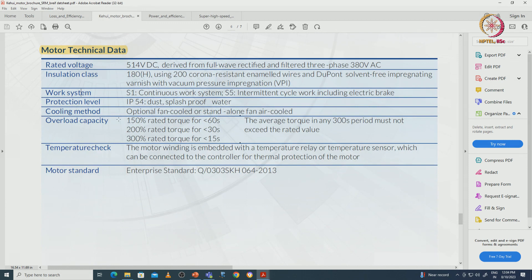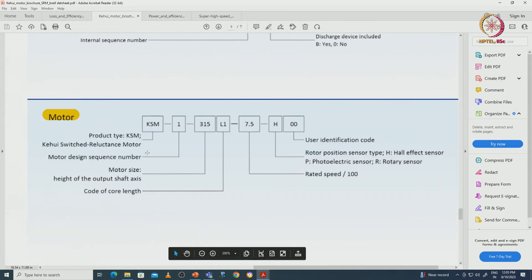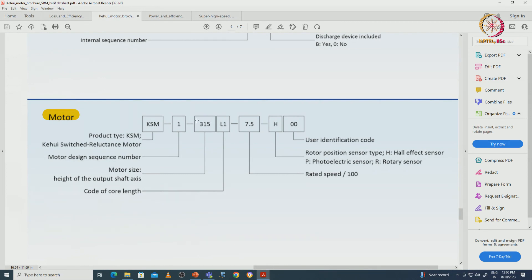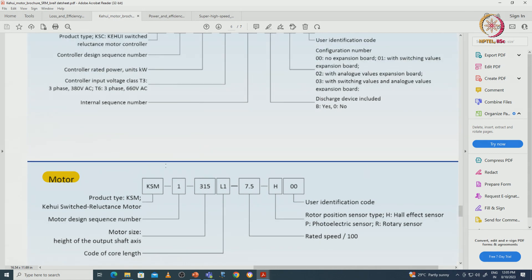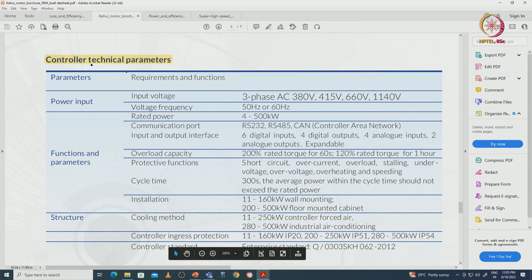Overload capability is: 150% rated torque for less than 60 seconds, 200% rated torque for less than 30 seconds, and 300% rated torque for less than 15 seconds. Exceeding these limits may damage the machine. The motor standard notation is also explained: KSM represents the product type, 1 represents the motor design sequence, and 315 represents the motor size and height of the output shaft axis.